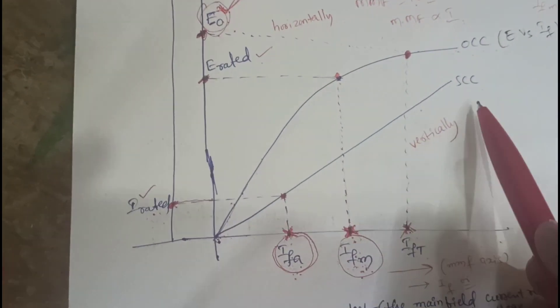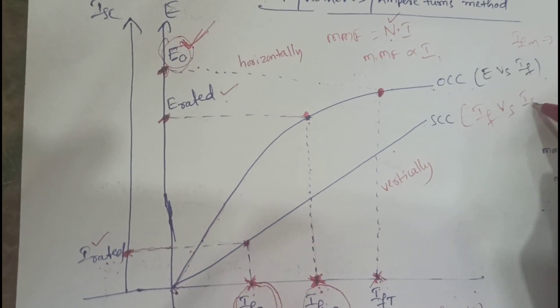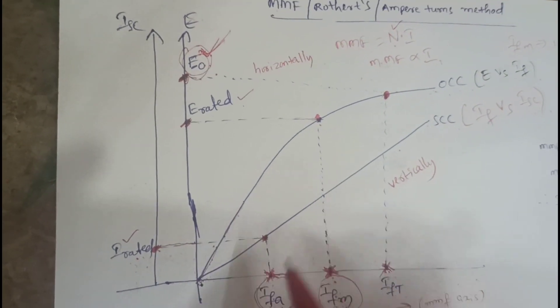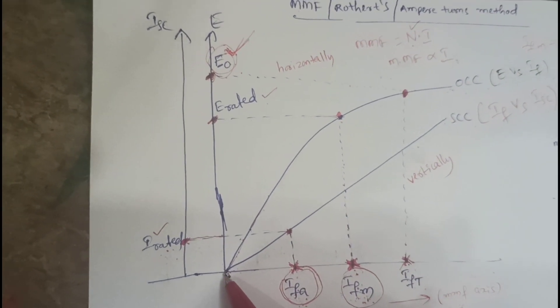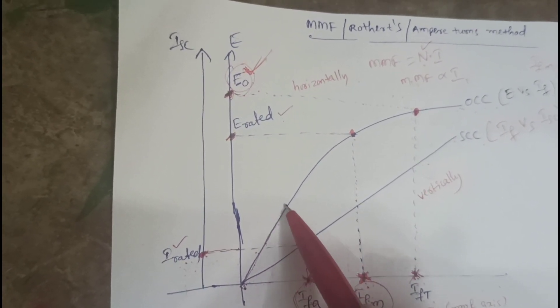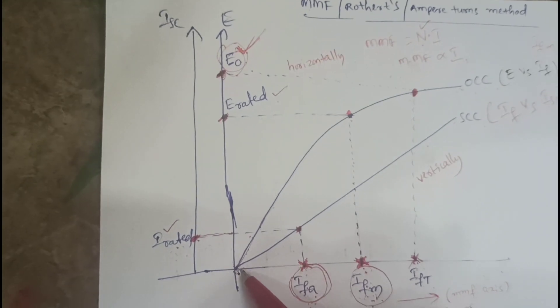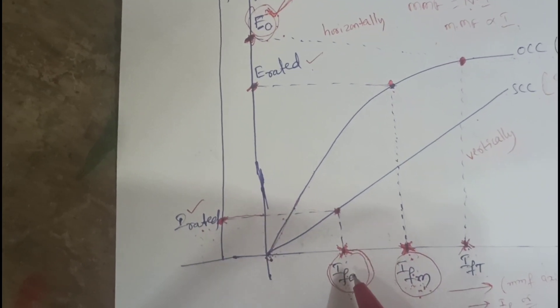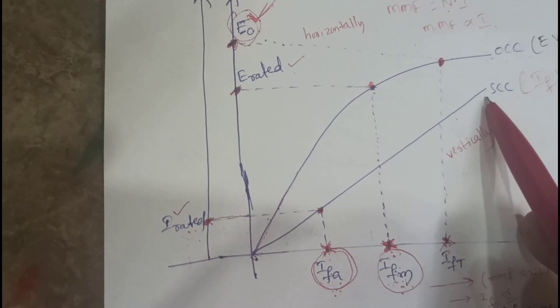The SCC characteristics are drawn between field current versus short circuit current ISC. First, draw the OCC curve: initially field current is zero, so induced EMF is also zero. As field current increases, induced EMF also increases. For the SC test, apply the short circuit current, note down the field current, and from these values draw the short circuit characteristics.